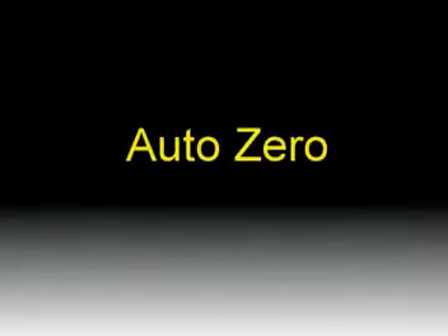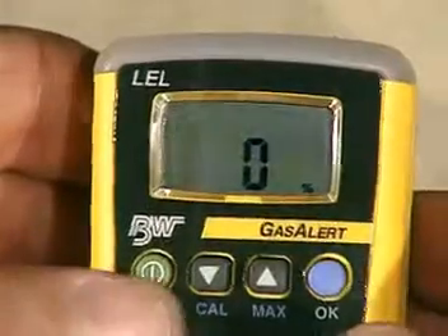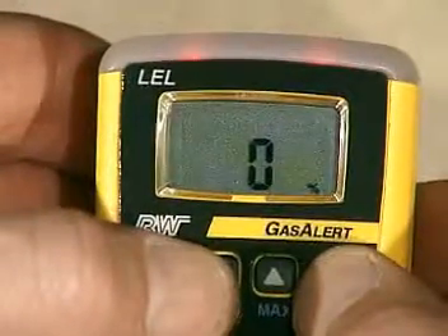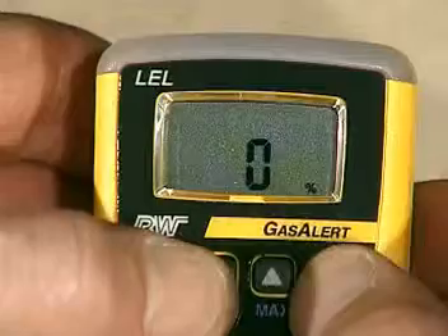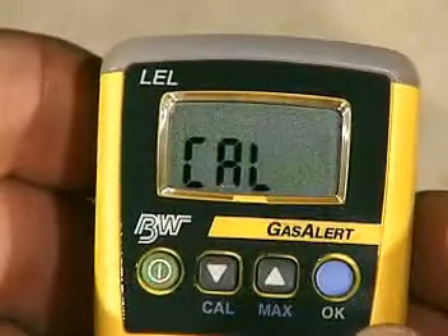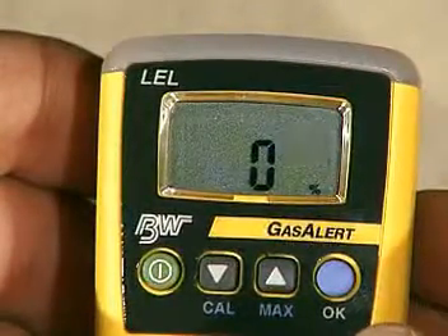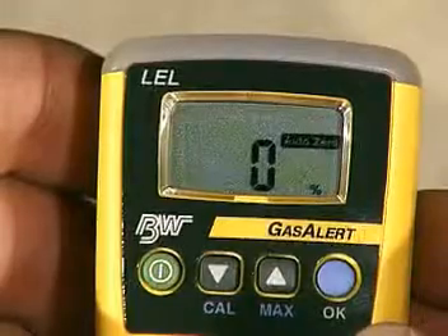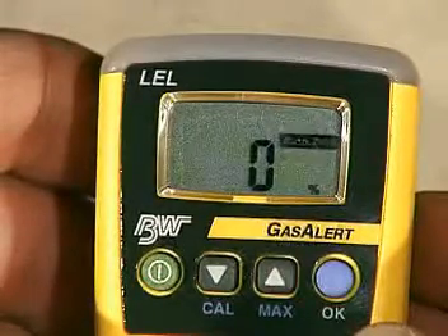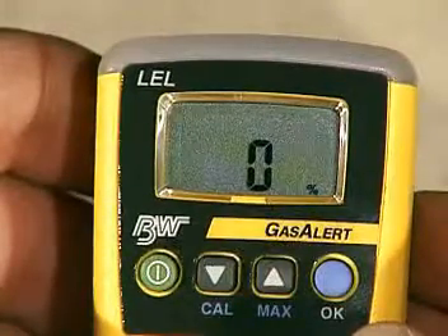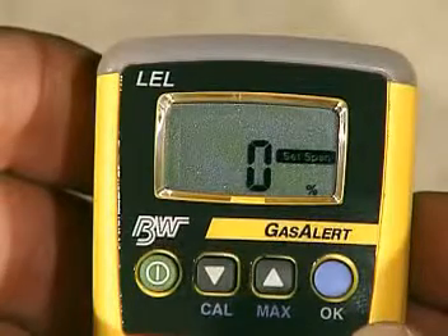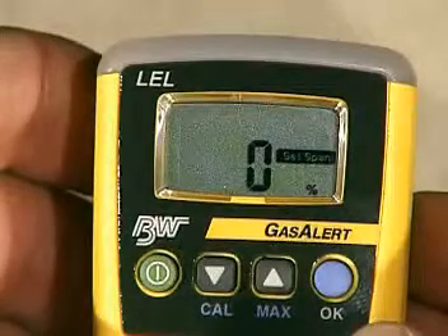Auto-zero the GasAlert-LEL at any time. In a clean atmosphere, free of background gas, press the OK and Cal buttons together until the LCD reads Cal. The auto-zero icon flashes. 2 beeps advise a successful zero. Press the OK button to exit or proceed to set span.